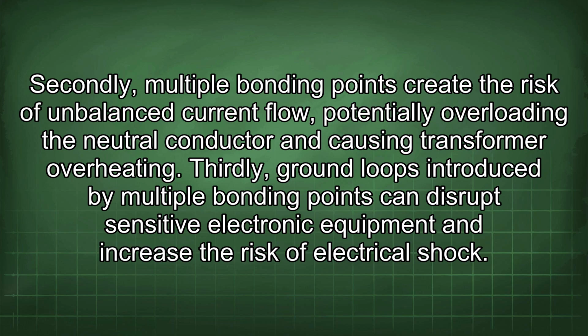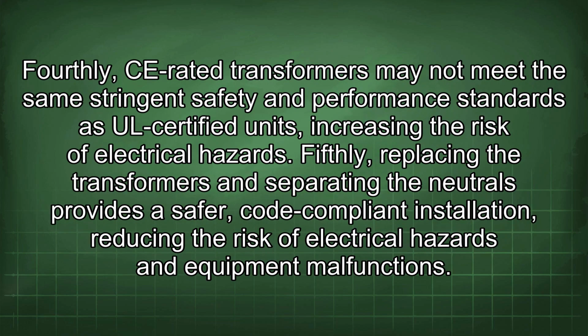Secondly, multiple bonding points create the risk of unbalanced current flow, potentially overloading the neutral conductor and causing transformer overheating. Thirdly, ground loops introduced by multiple bonding points can disrupt sensitive electronic equipment and increase the risk of electrical shock. Fourthly, CE-rated transformers may not meet the same stringent safety and performance standards as UL-certified units, increasing the risk of electrical hazards.